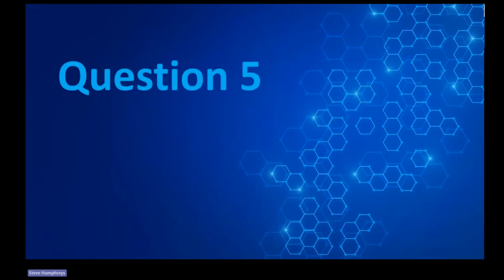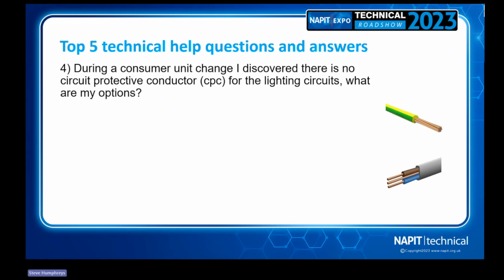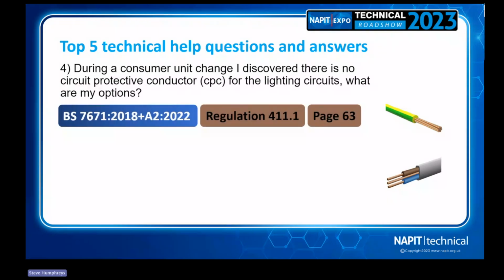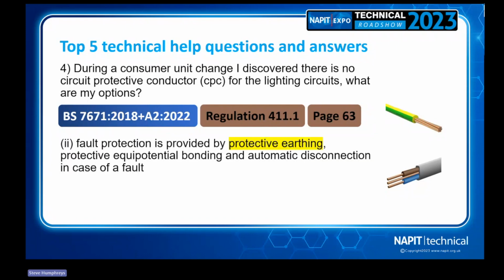And the last question we got, which is again a really good question from one of our members: during a consumer unit change, I discovered there is no circuit protective conductor, CPC, for the lighting circuits. What are my options? So again, if we look at what the regulations say in 411.1 on page 63, we can quite clearly see that indent 2 says fault protection is provided by protective earthing, protective equipotential bonding, and automatic disconnection in case of a fault, so ADS.